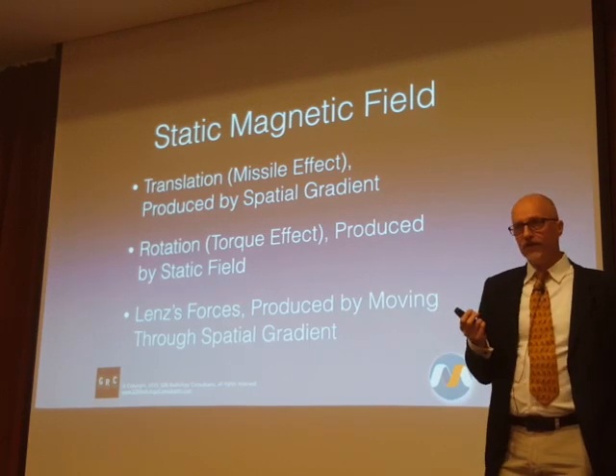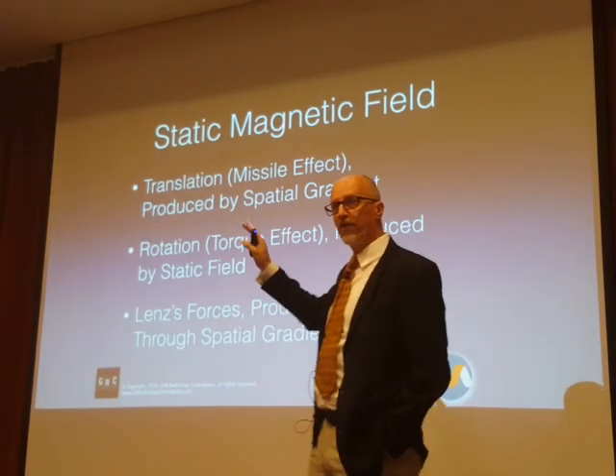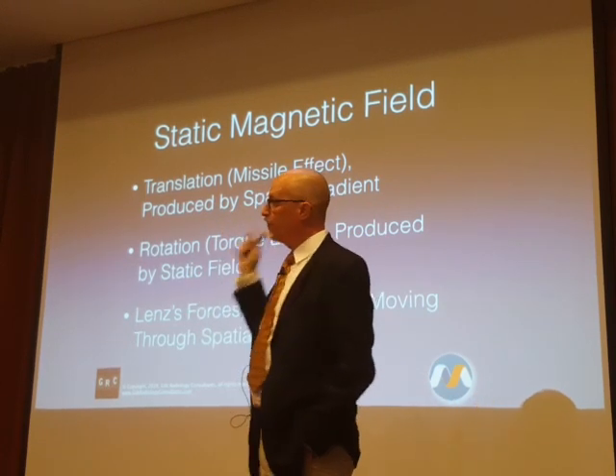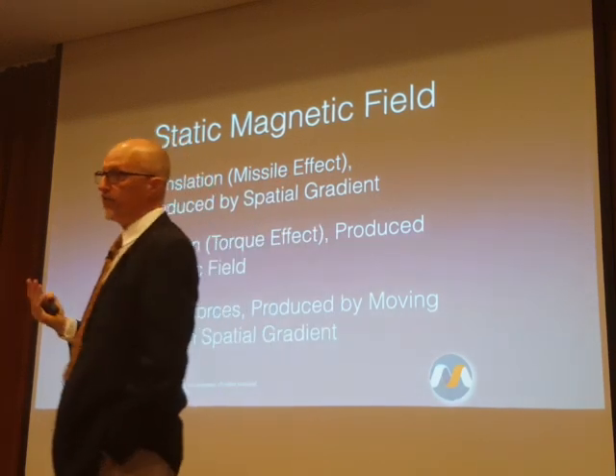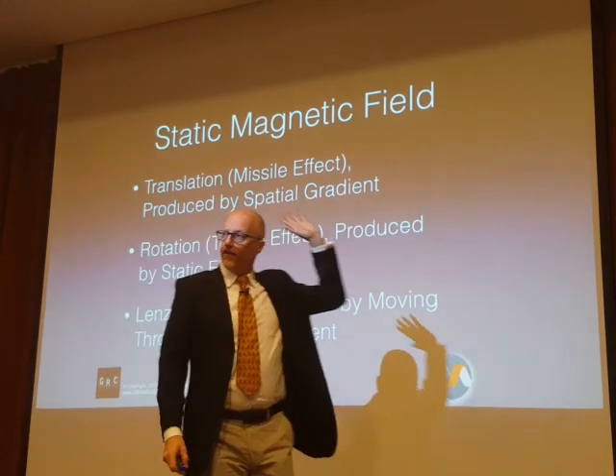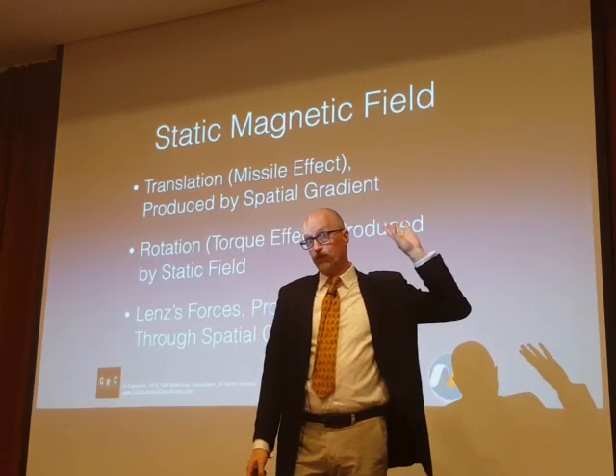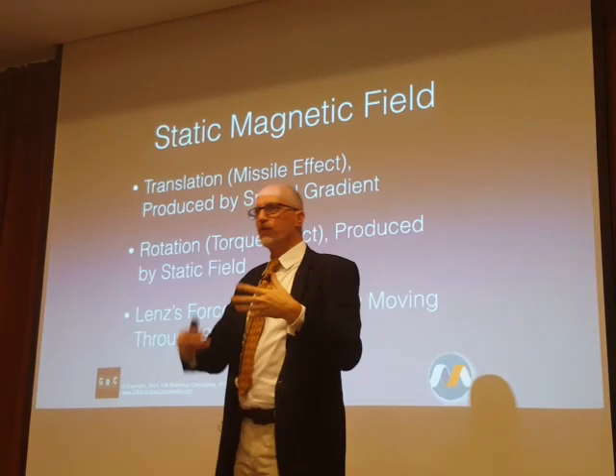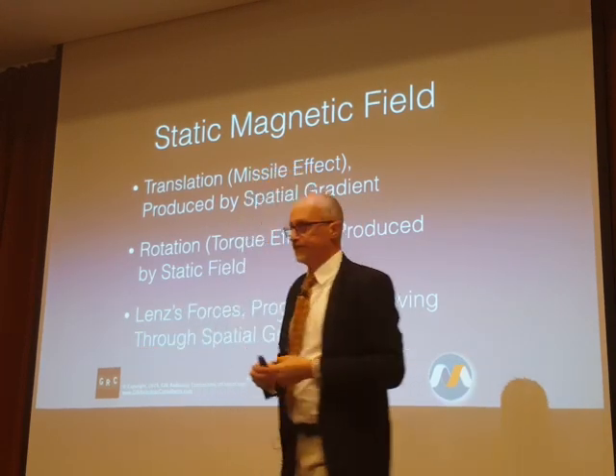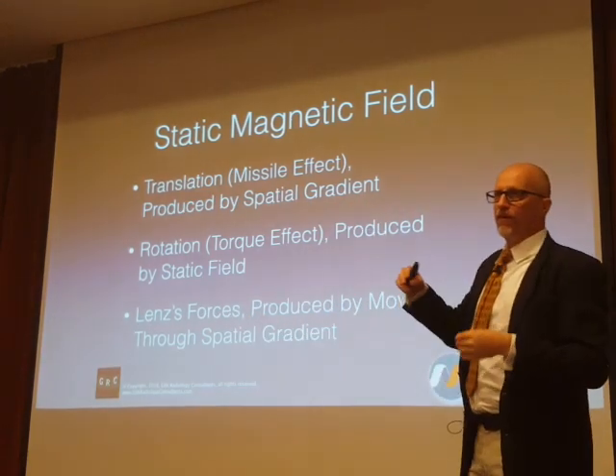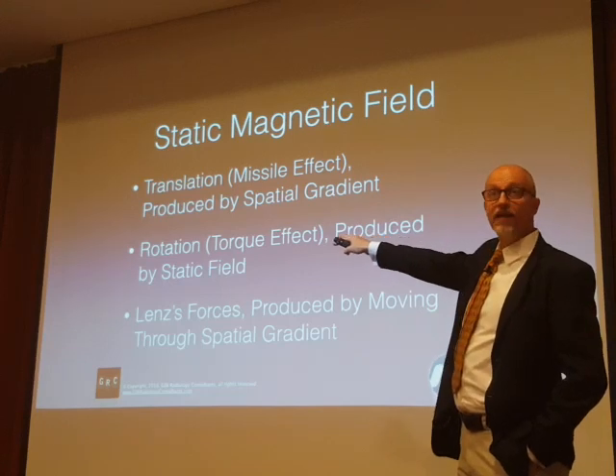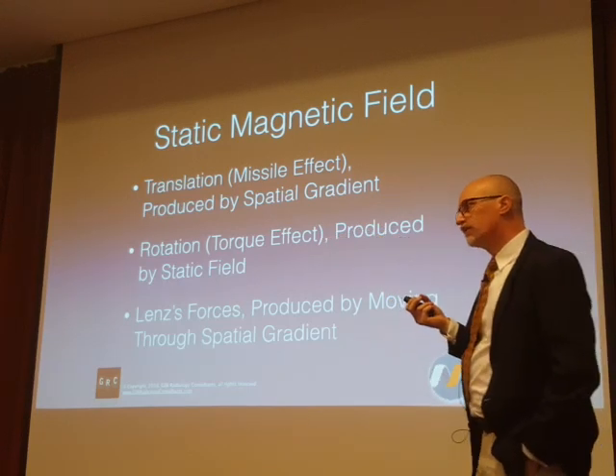For the static magnetic field, it is the portion, one of the three, that is responsible for translation, the missile effect, things going flying. That is, in most objects, just a direct product of the properties of whatever that object is, and the object's interaction with the magnetic spatial gradient. The 720 Gauss per centimeter, 7.2 Tesla per meter, those are measures of spatial gradient, and that is the factor that is principally responsible for the translation or the missile effect, an object that goes flying.